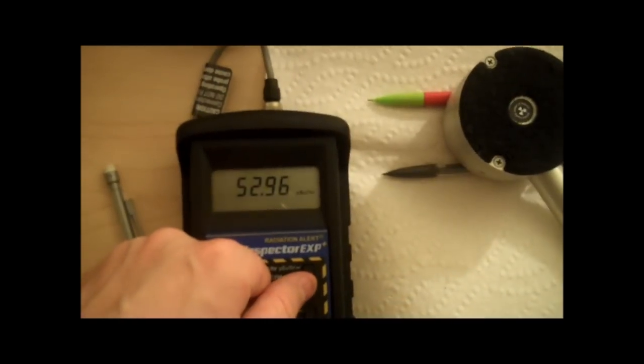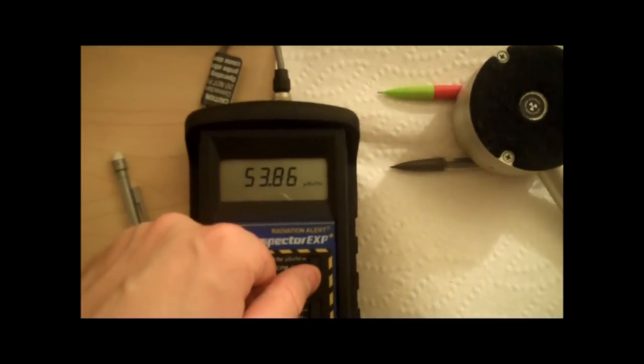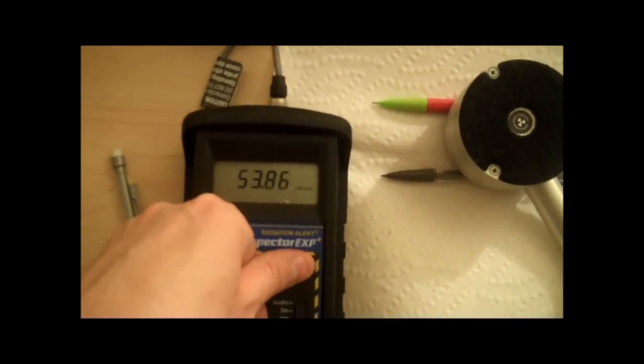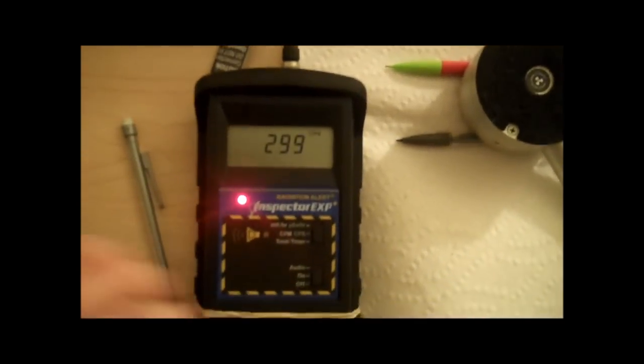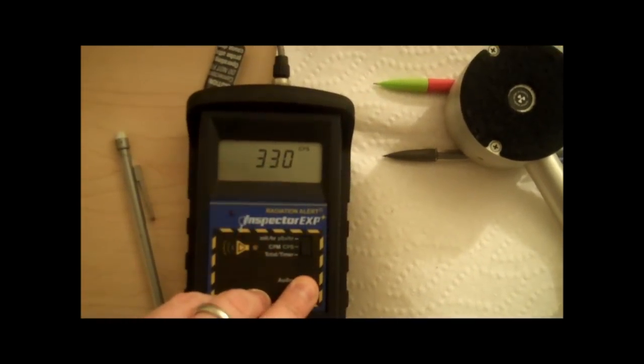Let's go test. You go over here to the Geiger counter. Geiger counter says 52 point whatever microsieverts. That's what it thinks. Let's change it so it's correct. Cut it off. Press the plus button right here. While holding the plus button, cut the thing back on. Let's cut the volume off though, good God.